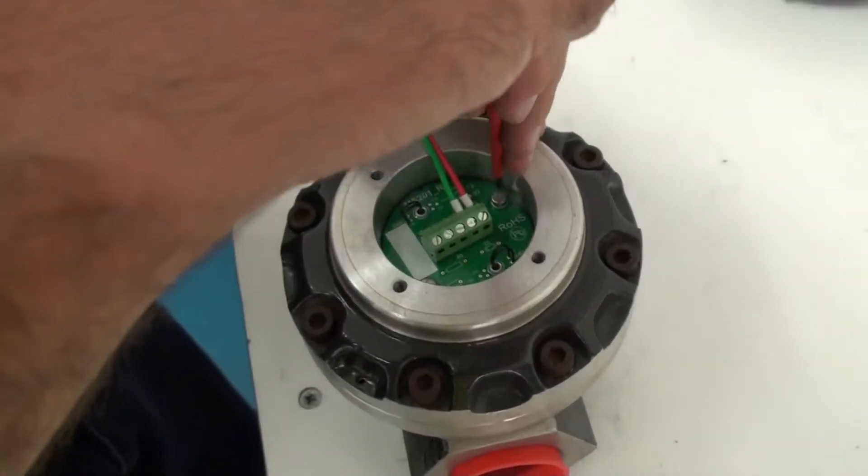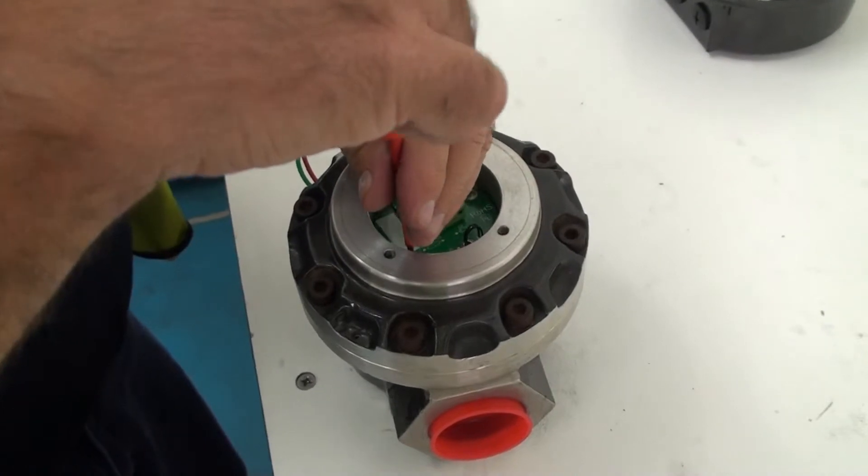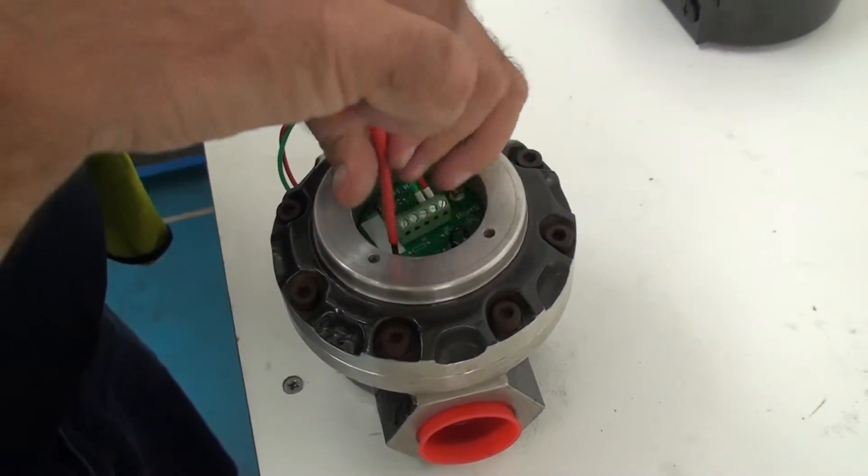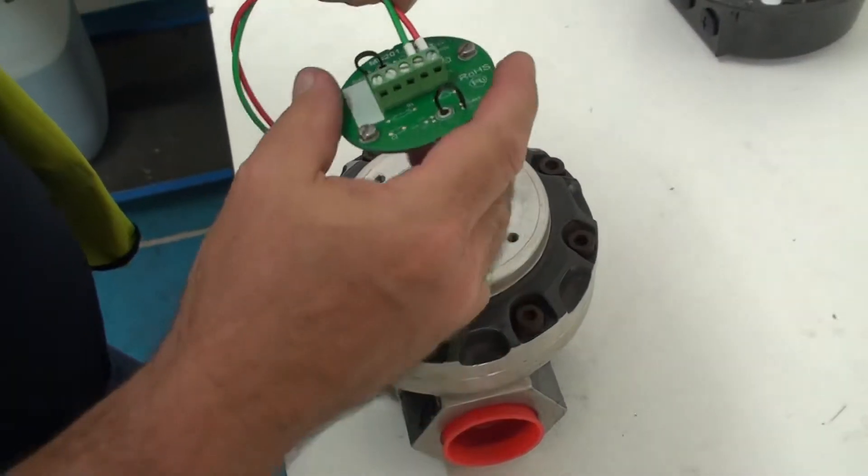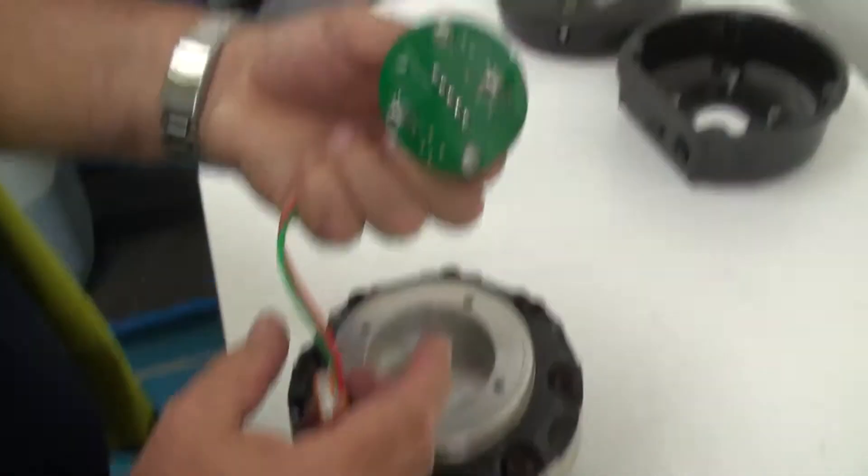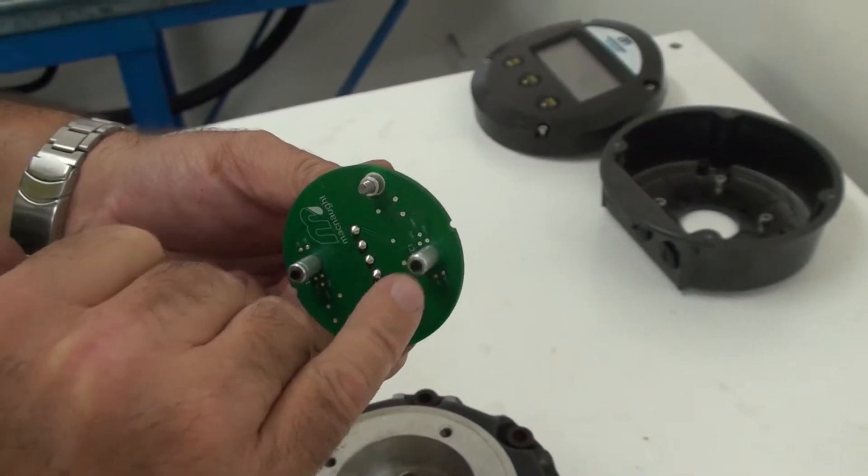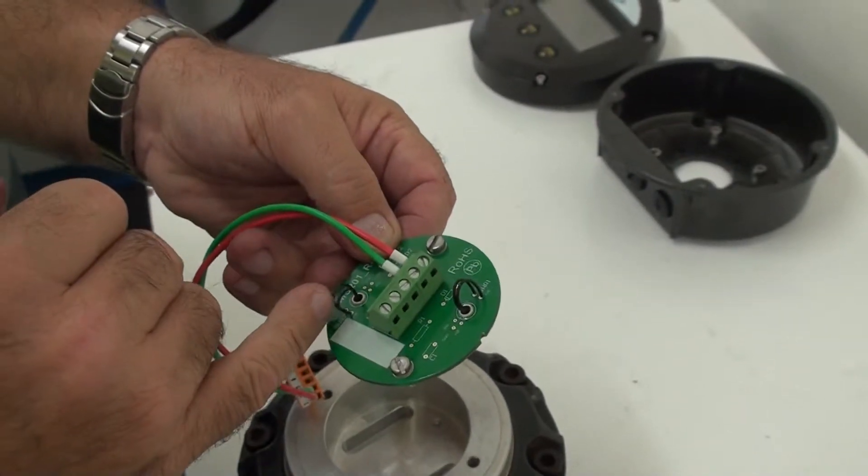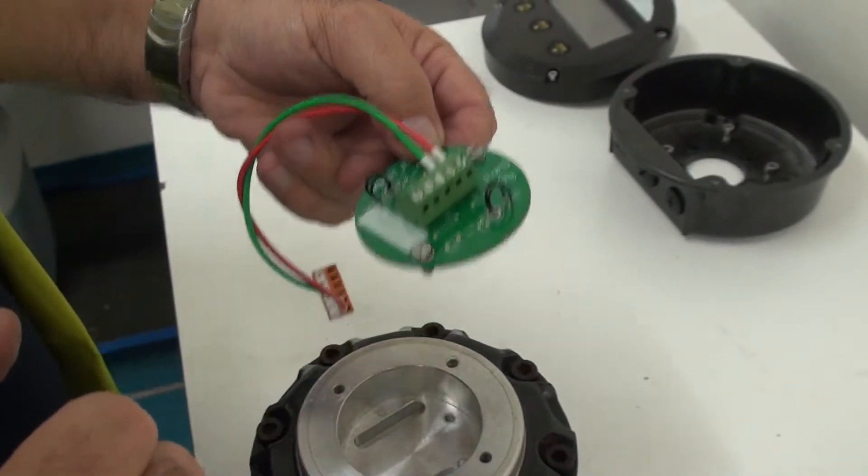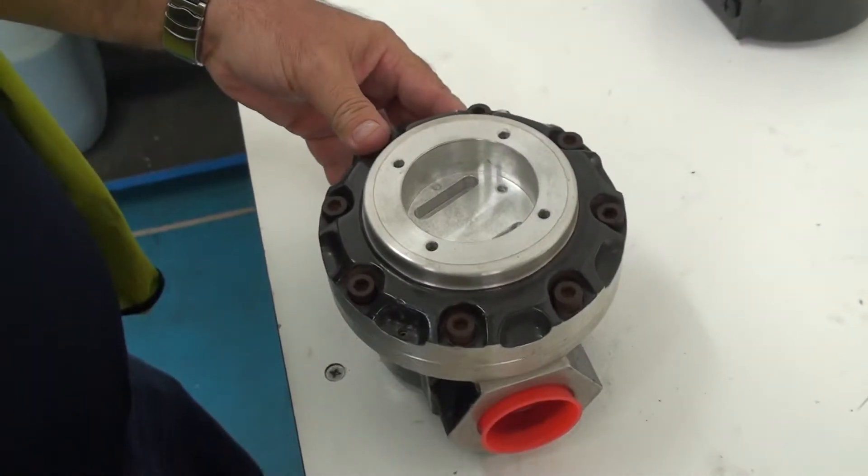So what we'll do is we undo the two screws that hold this pulse board onto the flow meter and this will allow us to remove that pulse board out of the flow meter. Now if I turn it over you can see the little reed switches here in the little aluminum standoffs. So this board is a dual reed because it has two sets of little wires. I'll put that out on the bench and out the way.